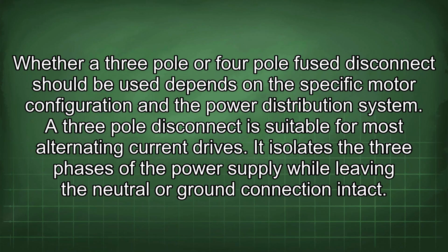Whether a 3-pole or 4-pole fused disconnect should be used depends on the specific motor configuration and the power distribution system. A 3-pole disconnect is suitable for most alternating current drives. It isolates the 3 phases of the power supply while leaving the neutral or ground connection intact.